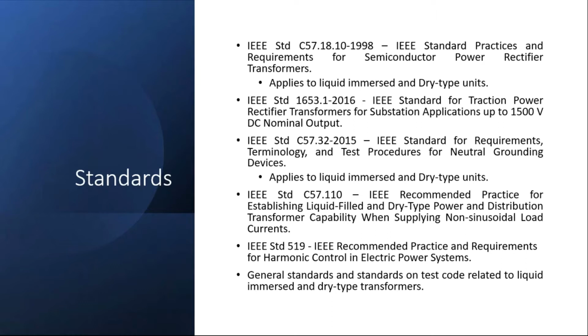As we know, grounding transformers have a special winding, zigzag type of connections, and this comes into effect when there is a fault. So this standard requires certain things to be specified in the specification. For example, the current flowing in the neutral, the time the current flows, and the zero sequence impedance in ohms. And the next two standards, C57.110 and standard 519, are dealing with the non-sinusoidal load current requirement and the harmonic enhancement factors. And then we have limits on voltage and current harmonics covered in IEEE standard 519. So all these standards cover the specific points, and the general standard C57.12.00 and 12.01 is applicable to these transformers.